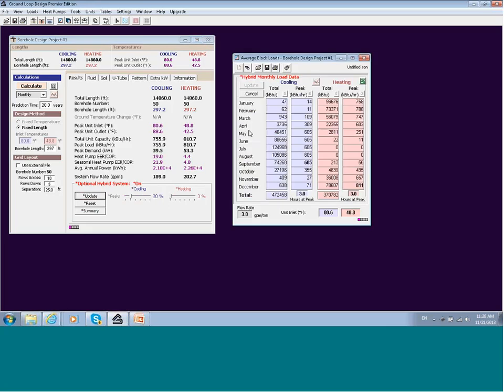If we look at the monthly loads, we can see that where the peak decapitation has happened, it started in the month of May and gone through September. See how these are flat here. So these months have been affected peak-wise, and they've also been affected on the annual level. The other months of the year, the winter and early spring and fall months, haven't been affected at all by this particular design. If I want, I can graph the data to kind of look at what's going on.